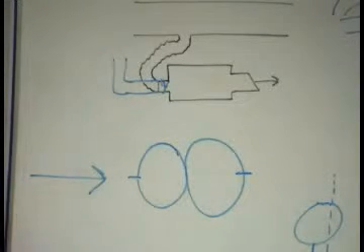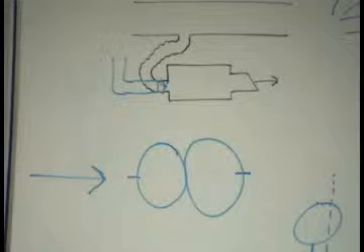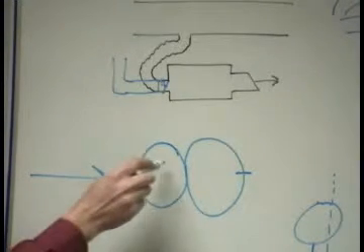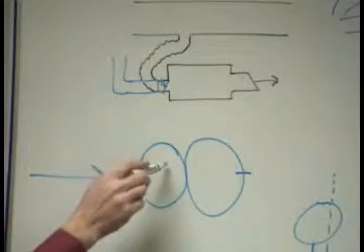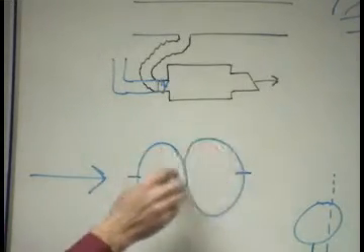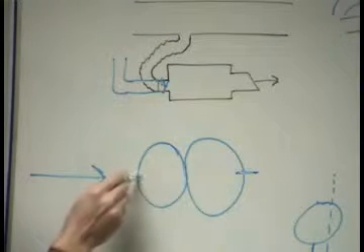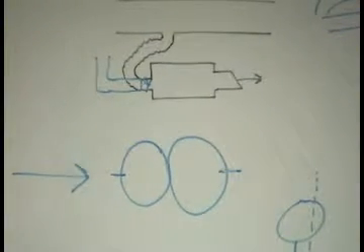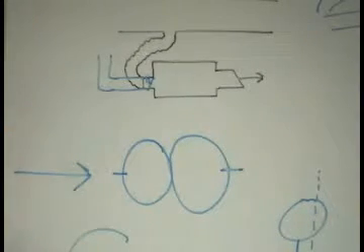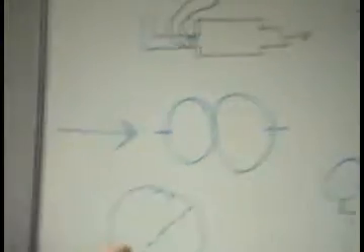Now, the box manufacturers will tell you that we don't use a pitot tube. We use a special amplifying, insert your trade name here. But when you open it up and look at it, all you see is this plastic thing. If I'm looking at a cross section here, here's one tube and here's another tube. They're back to back. One of them has holes on one side going downstream. The other one has holes going upstream. So if I'm looking down the duct, you've got this thing here and there's a bunch of holes along there. And along the back side, you have the exact same thing.